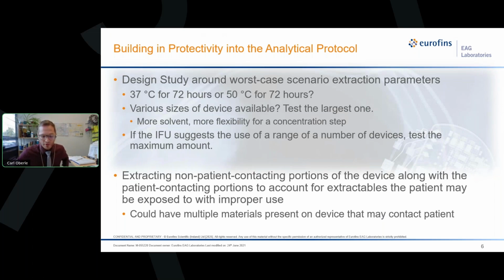And this can be useful, especially if you don't have a uniform device. Let's say it's all stainless steel. Say you have a stainless steel probe and then there's a rubber handle or something like that. If we test some of that rubber as well, we can generate an extractables profile that will include some of those components too. So if there was an instance, like Claus was saying earlier, where a surgeon places a device down in a patient and they come in bodily contact with the rest of the device, the testing facility has already accounted for that, and we have an extractables profile that includes some extra portions of that device. So, little things to keep in mind when you're designing your study on the front end.